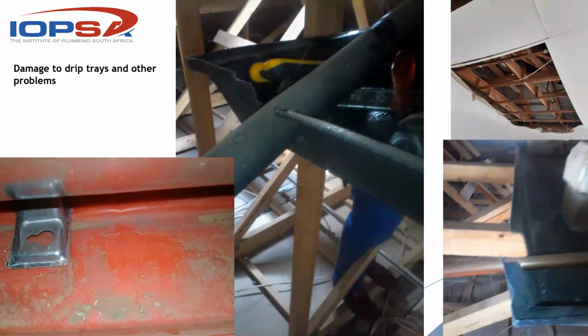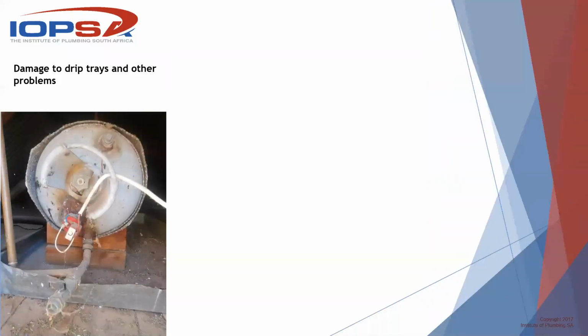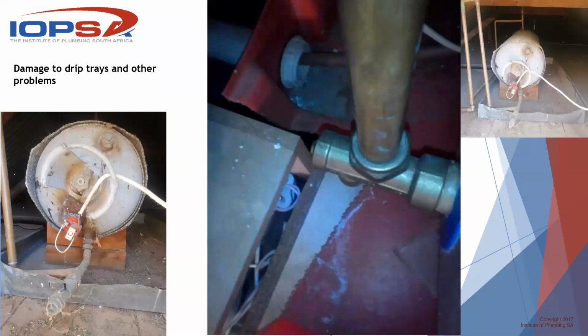And then these other pictures, you can see it doesn't need explanation. When you've got a drip tray to serve the purpose of containment, and you cut it away, and you'll see in a couple of pictures' time an even worse example of that, obviously, guys, this defeats the purpose of having a drip tray completely. There's no point in the drip tray. And then just to show that it can be catastrophic if enough water is allowed to leak onto a ceiling, it can be catastrophic.